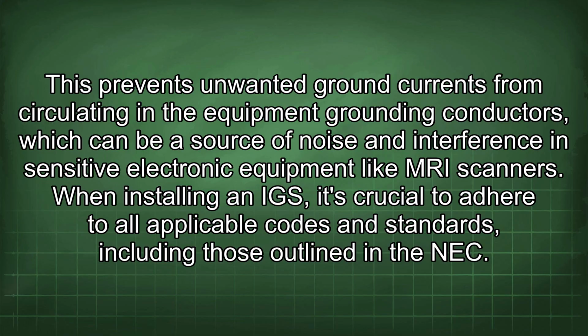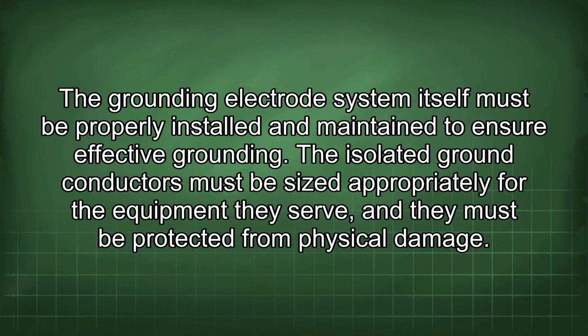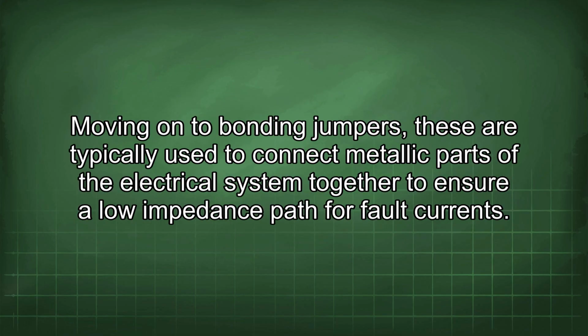When installing an IGS, it's crucial to adhere to all applicable codes and standards, including those outlined in the NEC. The grounding electrode system itself must be properly installed and maintained to ensure effective grounding. The isolated ground conductors must be sized appropriately for the equipment they serve, and they must be protected from physical damage.